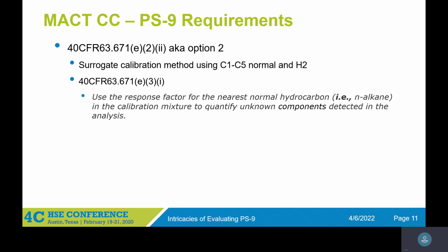So if you go with this method, a lot of sites interpret this as, all right, for our net heating value calculation, anything that is not C1 through C5 normal or hydrogen, we need to classify as the nearest hydrocarbon to that analyte, and then use that hydrocarbon's value. For instance, ethylene would then be used as ethane in the net heating value equation required by MACT CC.